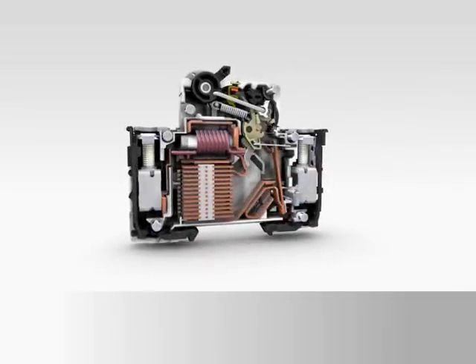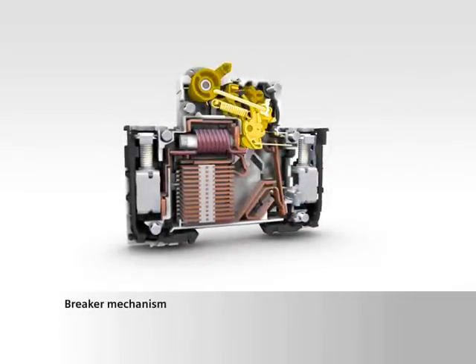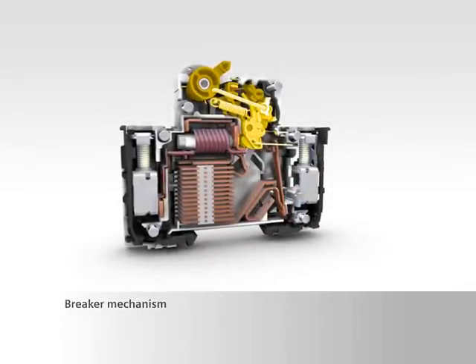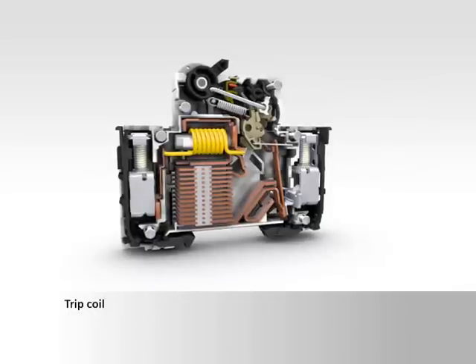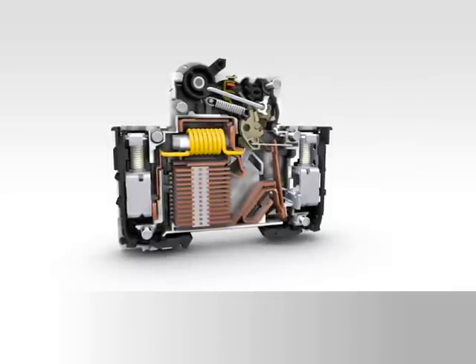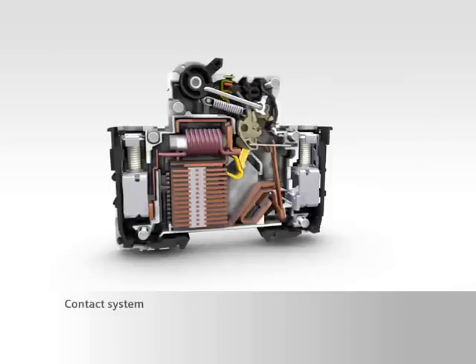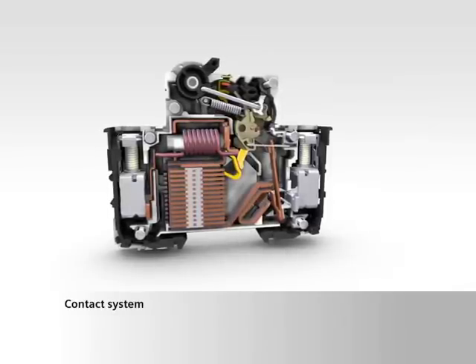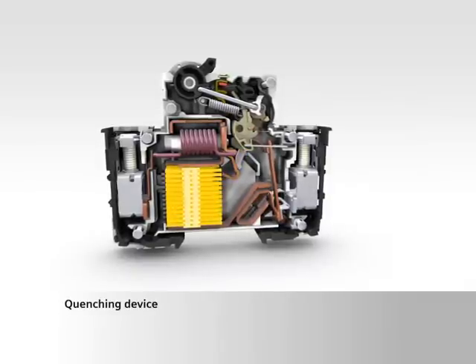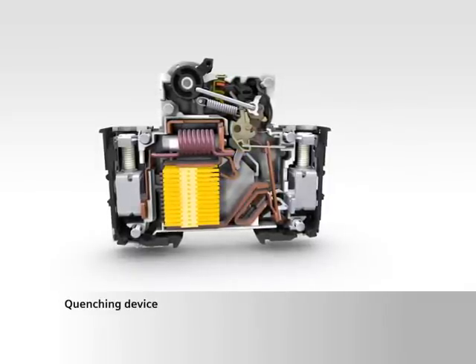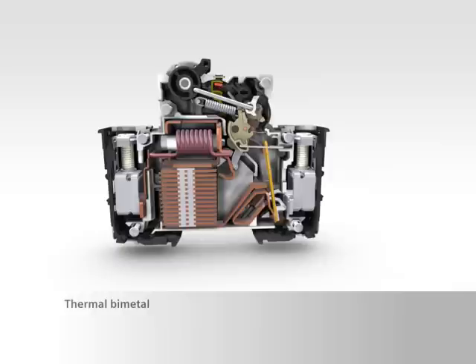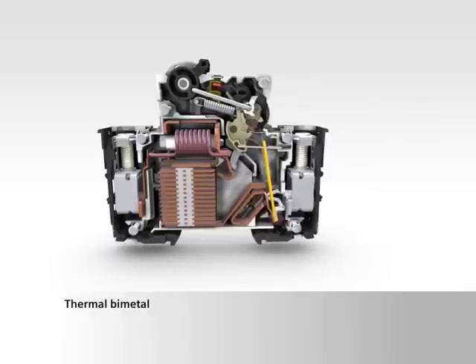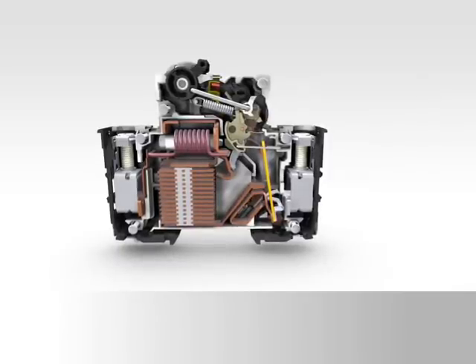This view shows functional components of a miniature circuit breaker. On the top right, the control device with a breaker mechanism. The trip coil for the short circuit tripping is located in the center, and to its right you can see the contact system. Underneath is the quenching device that is used to quench the electric arc which occurs during short circuits. The thermal bimetal is located to the right of this. This actuates tripping in the event of overload currents.